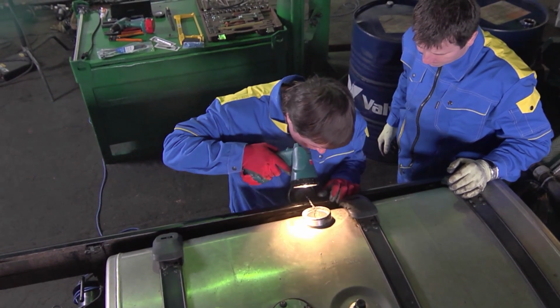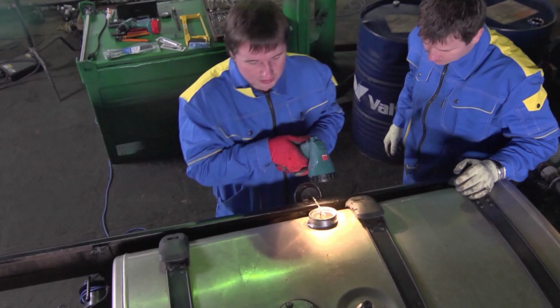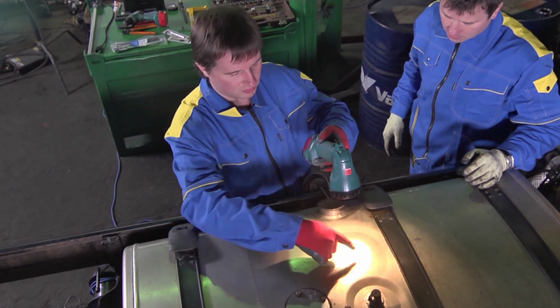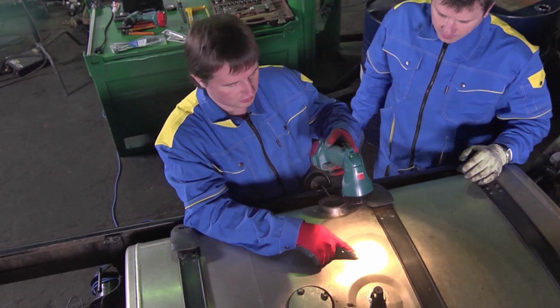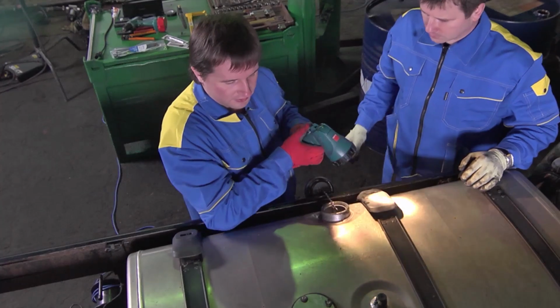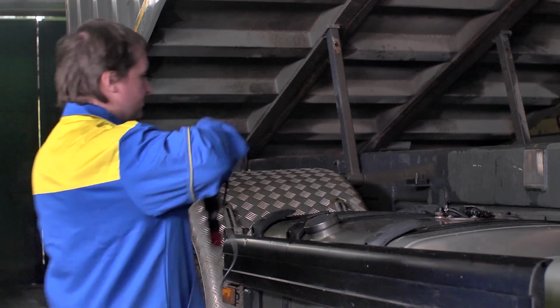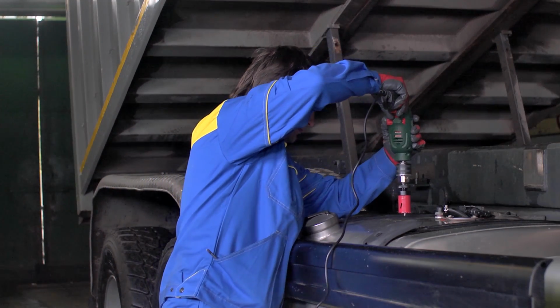We recommend installing the sensor in the geometric center of a rectangular fuel tank. This location minimizes any impact that fuel fluctuations inside the tank can have on the level measurements.